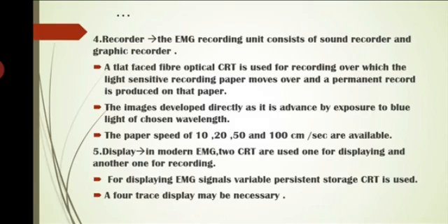Display. The modern EMG has two CRTs for display purposes: one for displaying continuously and another one for recording. For displaying EMG signals, a variable persistence storage CRT is used. A 4-trace display may be necessary for display purposes.